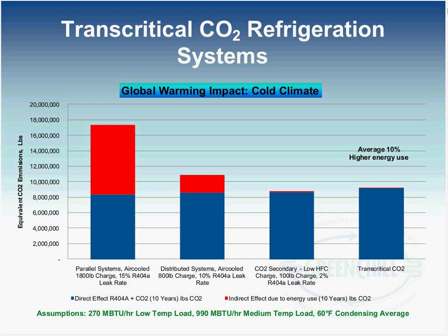This shows the impact from a warming potential in terms of refrigerant leak and energy consumption, in a colder climate such as Sweden and Denmark. You see how the transcritical system over to the right compares to the other systems in terms of energy and leak potential, or the direct impact on the environment from leaking the refrigerant. It's hard to see that there's a little bit of red at the top of that transcritical system as well.